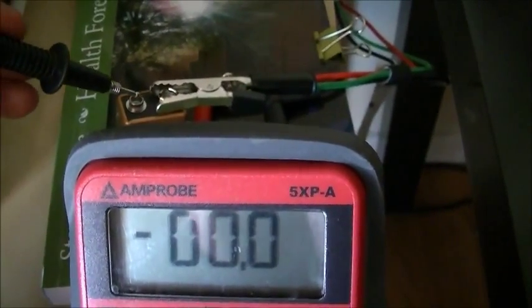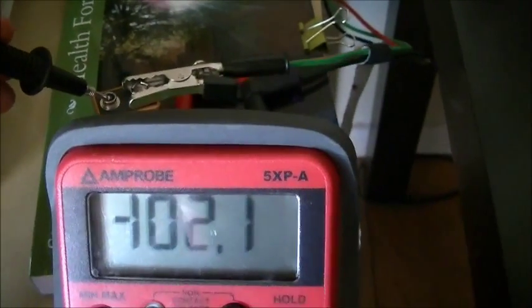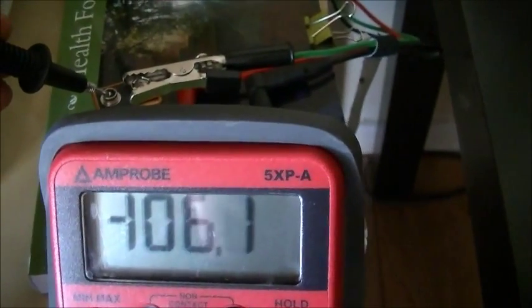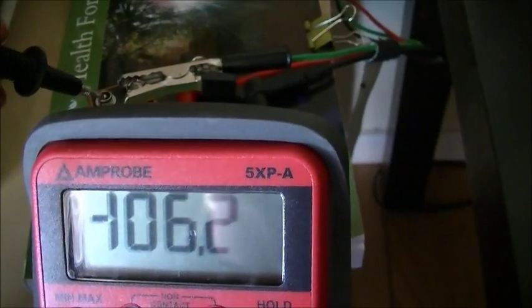I'm going to complete the circuit with this probe. Watch the meter as we connect. You can see we've got about 106 milliamps passing through this circuit, so we've got a very good connection.